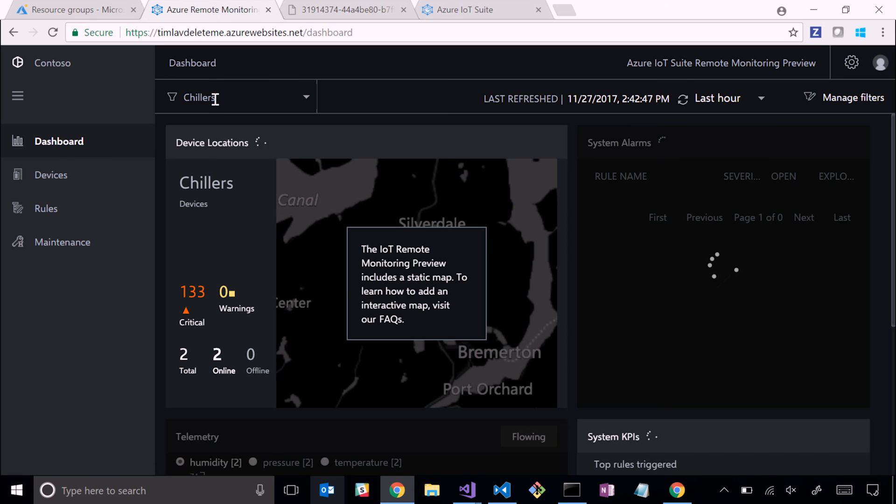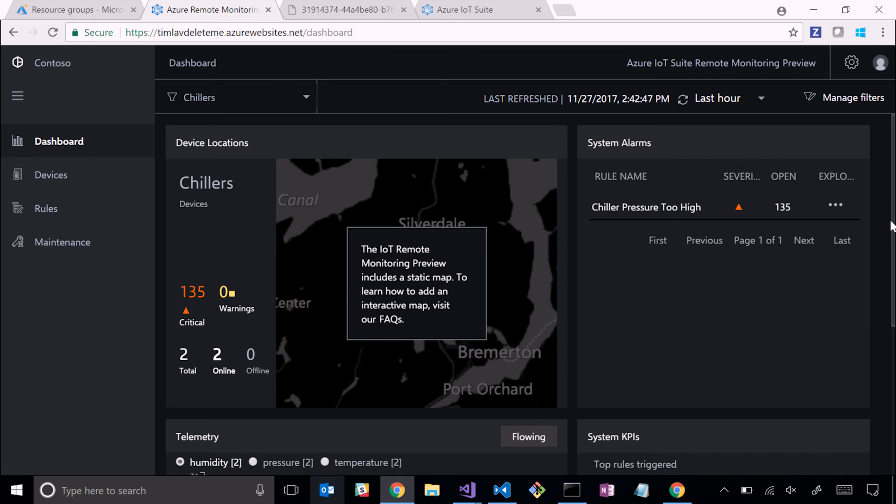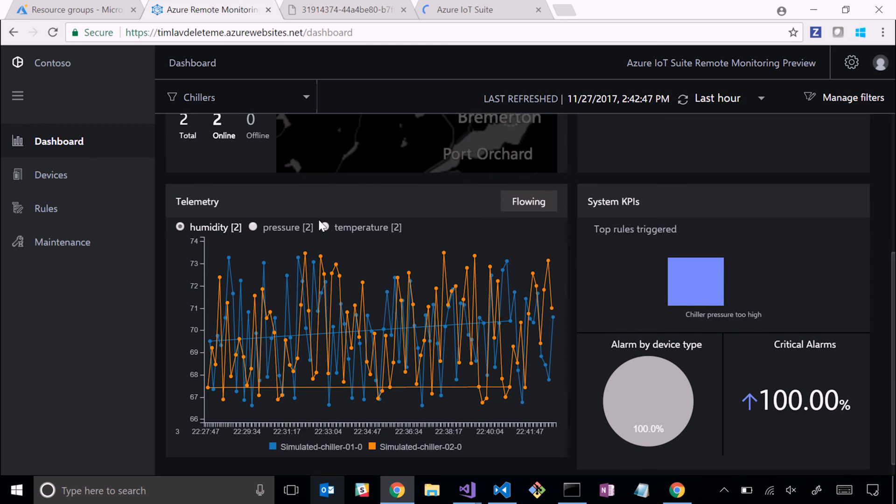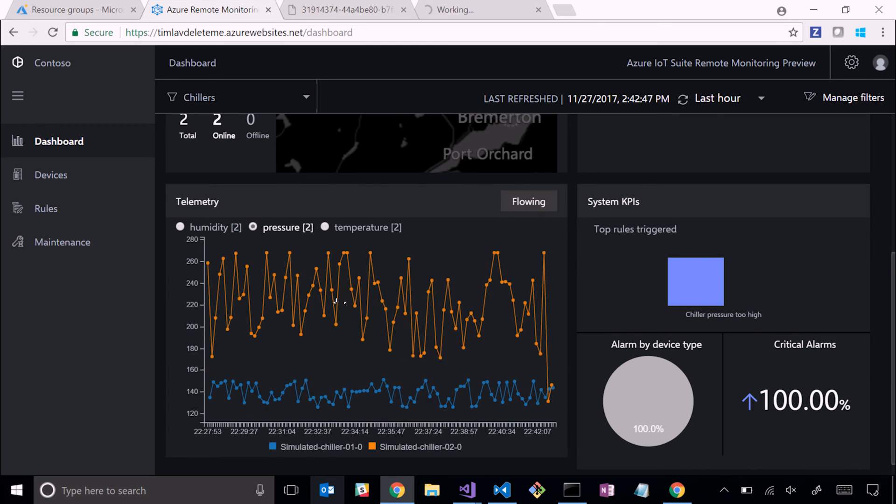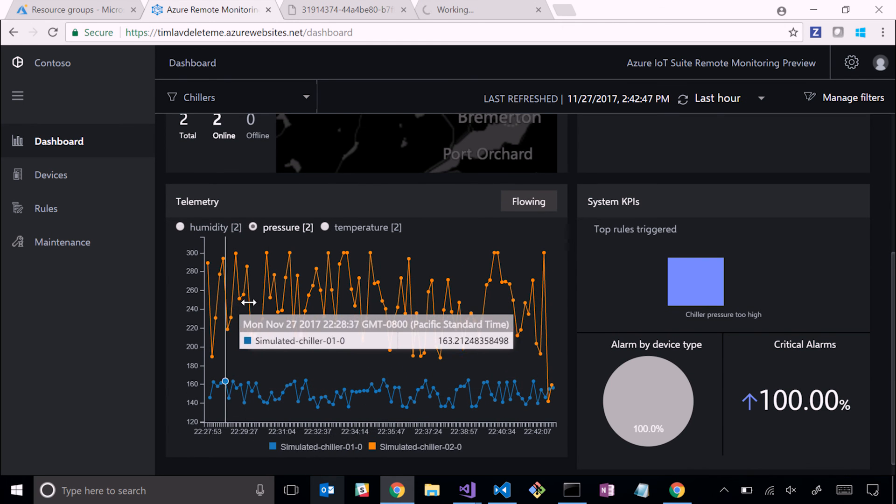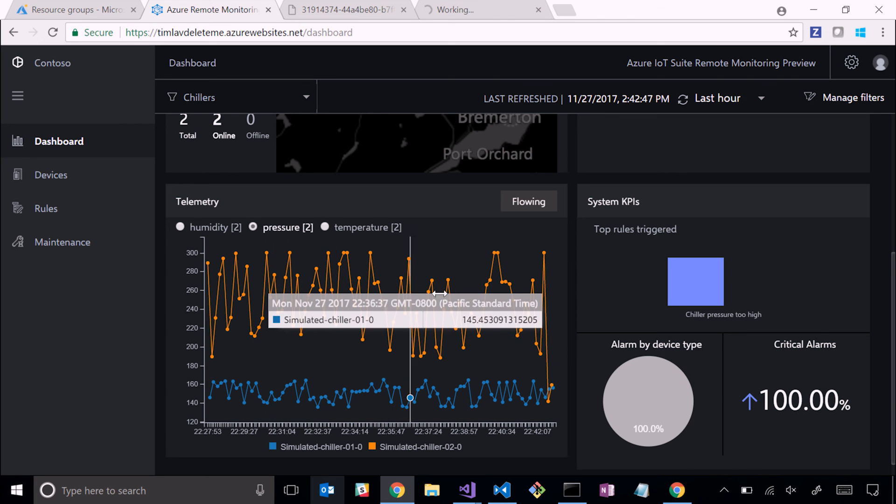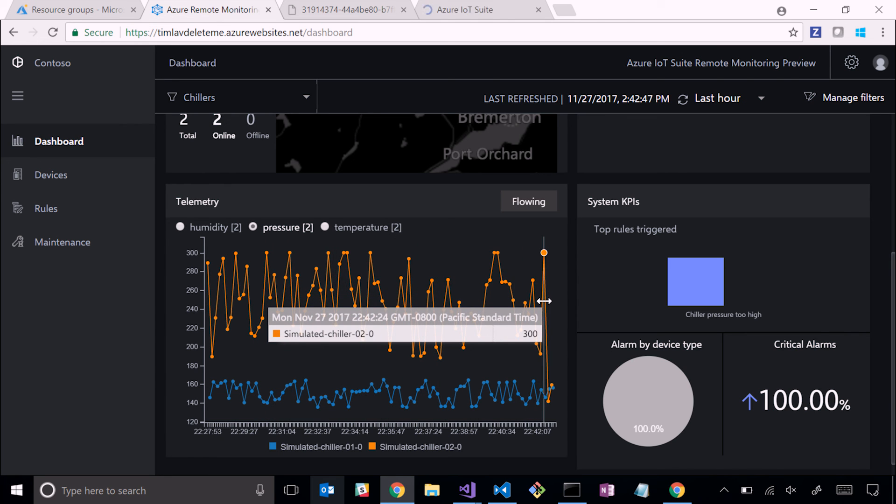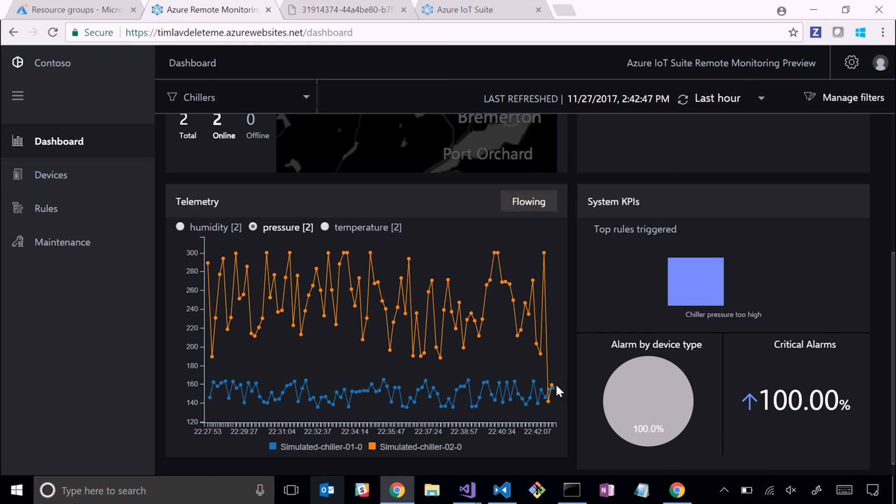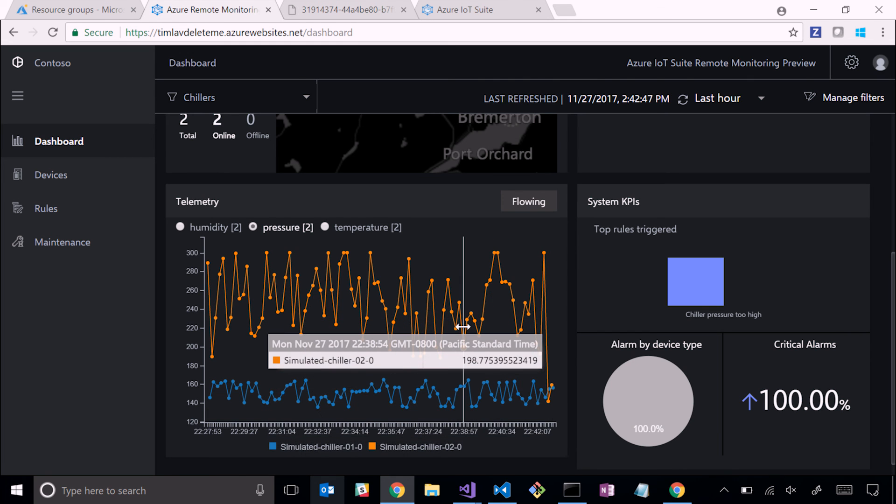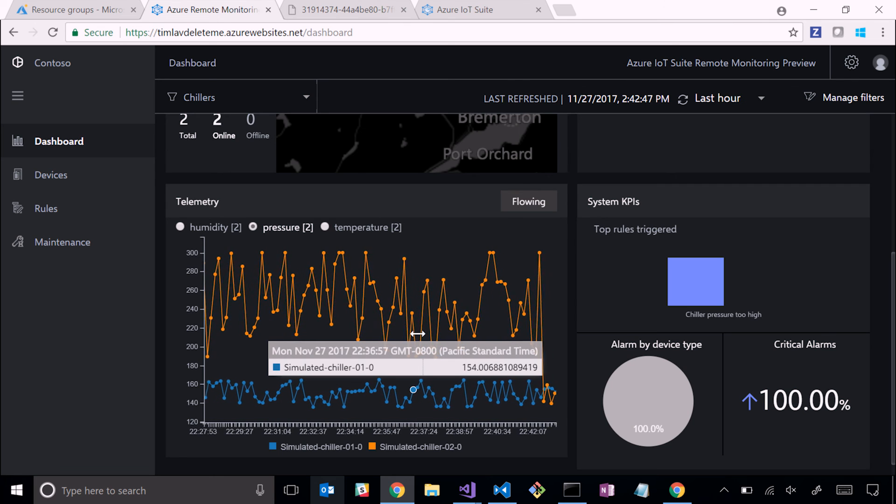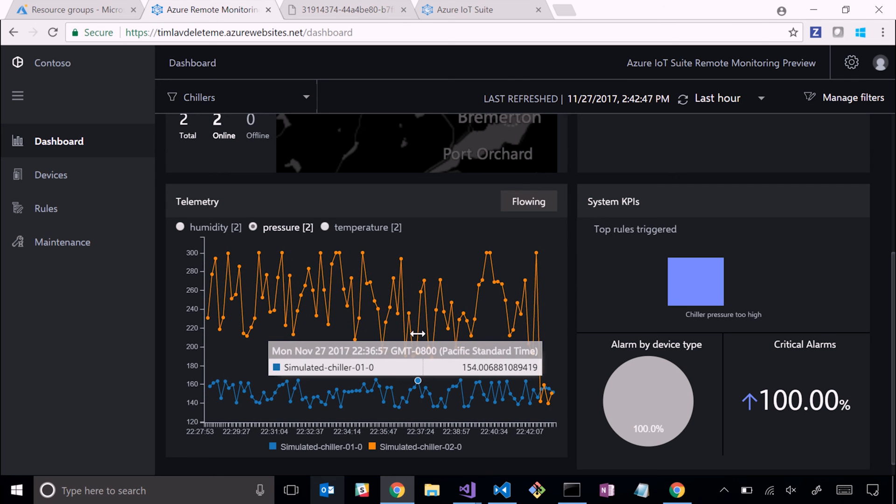If we want to see the results, if we came back to the dashboard, we're already filtered to just chillers. If we scroll down and look at just pressure, because it was pressure release, you'll notice here this is where it was in error. Then somewhere right about here we executed that method, and notice that now the pressure readings are way down. If you wait for 15 seconds or so, you'll see it grab another set of telemetry from the back end. Our mental model is we provision these devices, some of them are working as expected, some of them are in error, and then we offer a set of methods out of the box that fix the errors.